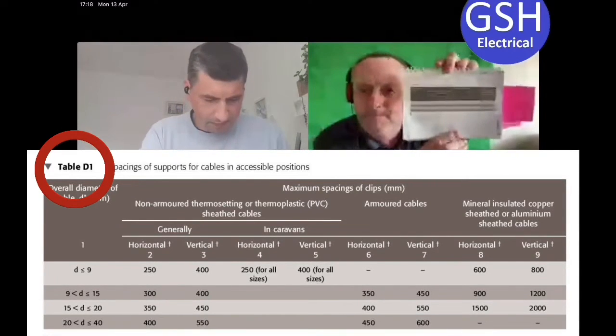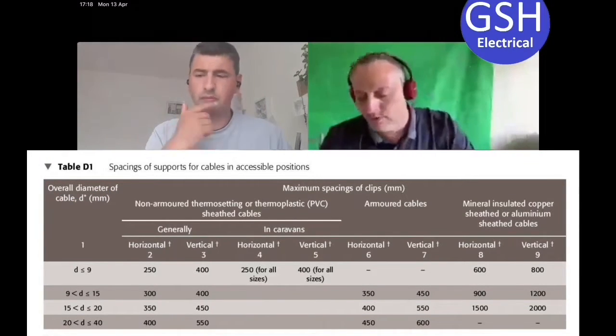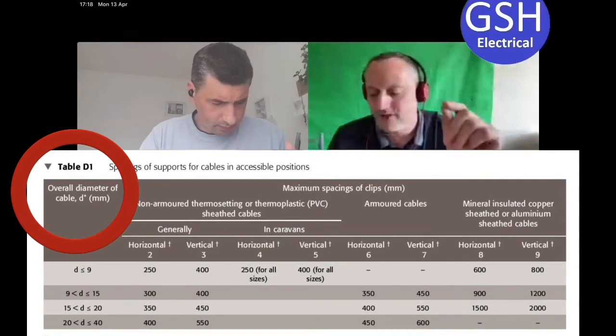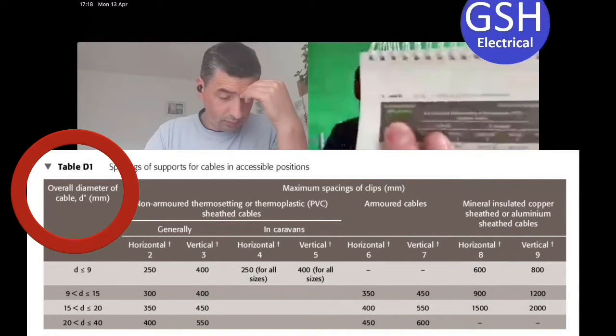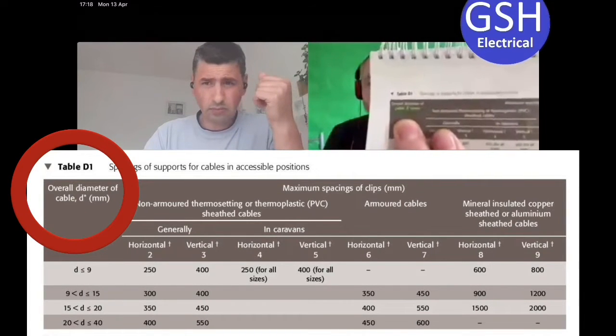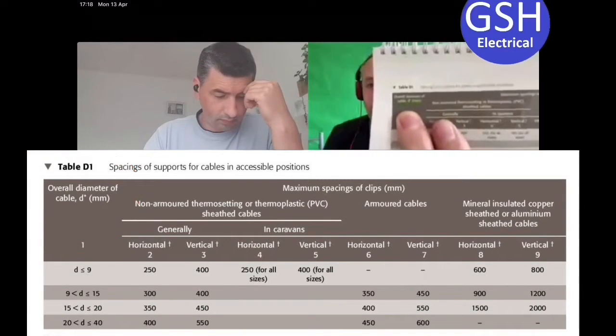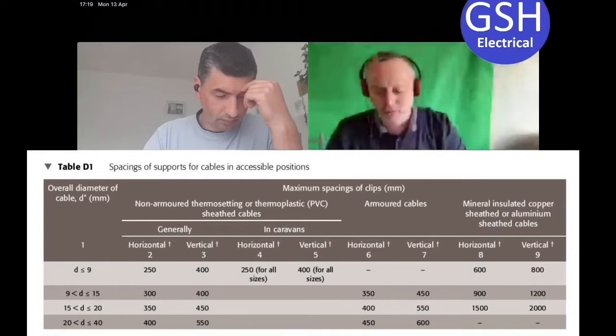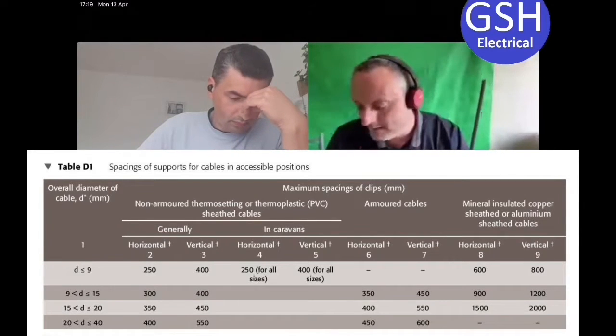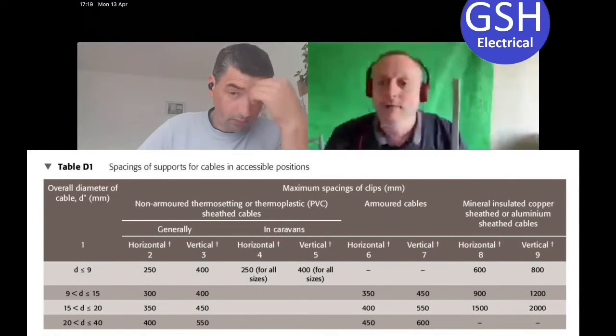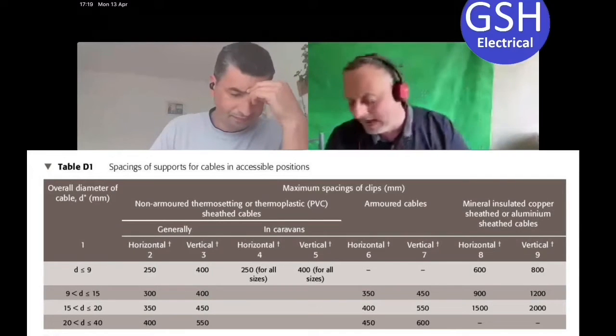Column one has a title that says 'overall diameter of the cable, d*, millimeters' - I've highlighted mine with fluorescent pen. It's the diameter of the cable. This is where people go wrong, because they look at column one and think 'cable size' - so if I've got a one mil cable they think use row one, if I've got a six mil cable they use row one. That's not the case because it's the diameter of the cable.